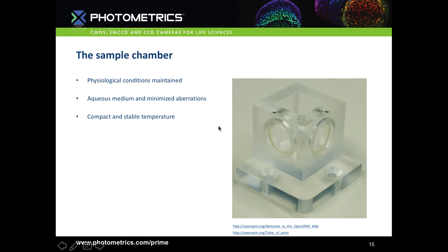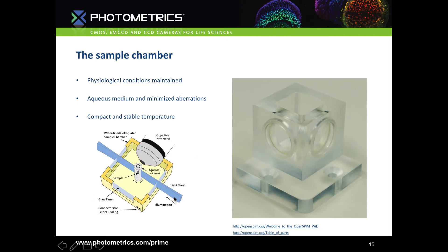A typical lightsheet sample chamber looks like a cube where the sample can be introduced from above. The chamber can be made both air and water tight, ensuring physiological conditions are maintained — for example, kept at 37 degrees if required. The lightsheet is introduced from the side illuminating the sample through the middle, and a water-dipping detection objective squeezes in through a circular opening that is then made water tight to preserve conditions within the chamber.